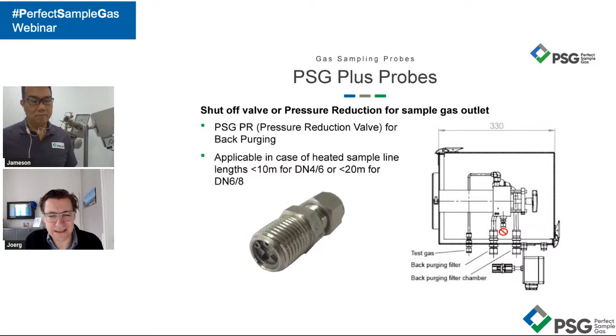The message here is, even if we choose the basic product line, it comes with the same filter and the same filter surface. But important with the plus is that it's also possible to include a back purging system, which will allow you to operate this with even lower. And here, this is the next thing, which is a pressure reduction valve. Because what happens, as James said already, the purge itself is important, there's a high pressure, and at the same time you want to protect your analyzer system, and one option for this is the pressure reduction valve, which we can see here.